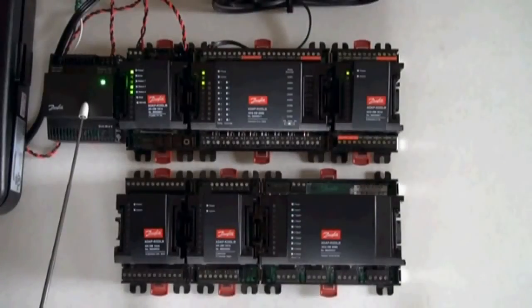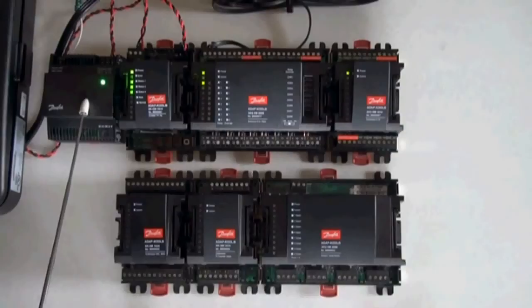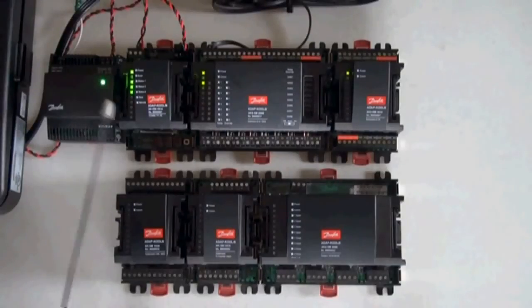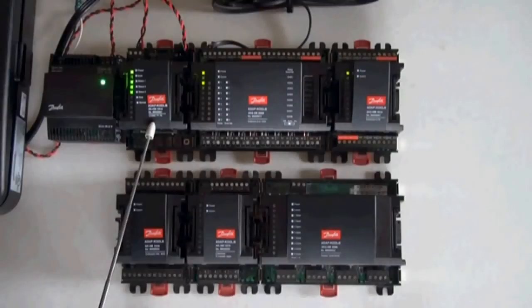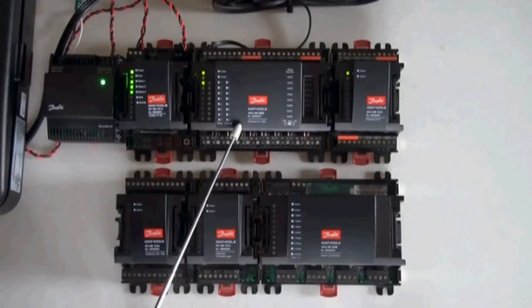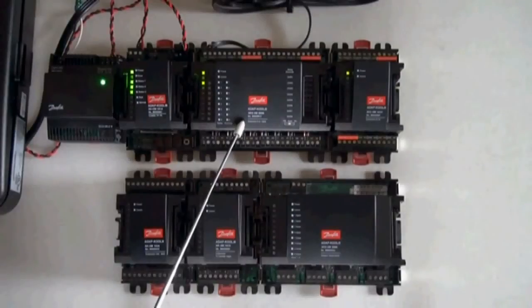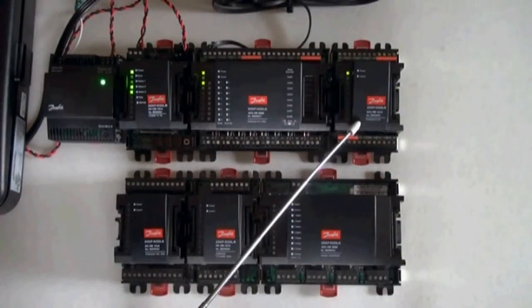Let's take a look at the AK2 modules used for I/O communication to the Danfoss 255. Here you see the 24 volt DC power supply. Next, the communication module. This module will start each group of boards. This module is usually known as the combo module. This one has 8 inputs and 8 outputs for relays. This board is used for inputs or dry contact digital inputs.